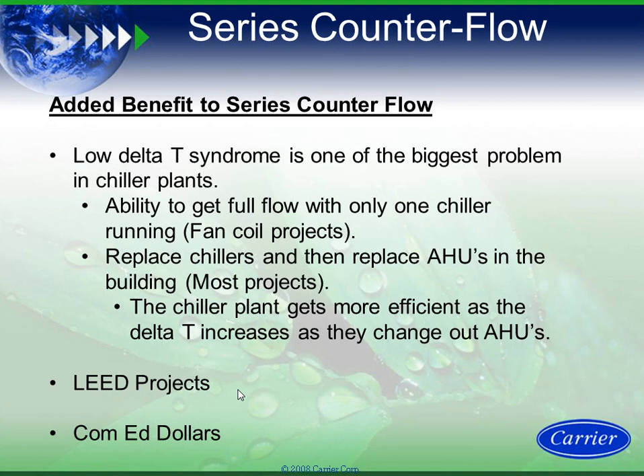However, the bad part about low delta T syndrome is sometimes if I'm running one machine and I need more flow on a parallel chiller plant, how do I get more flow? You get more flow by turning on a second chiller. So I may be running at, say, 50% load on that first chiller, and I need more flow because I have low delta T syndrome. So what happens? I now have to turn on the second chiller, and now I'm running two machines at 25% load to handle the flow. That's probably the worst operating point of a centrifugal chiller, and therefore I'm also over pumping, and all those bad things that go with low delta T syndrome itself.